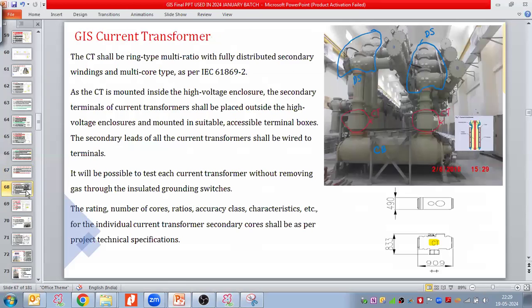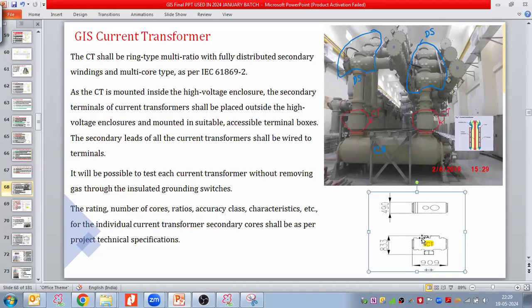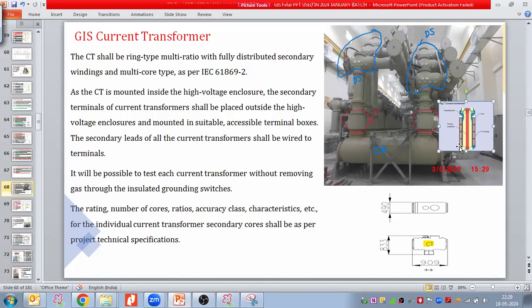Coming to the next equipment model, which is the CT model. First of all, how the CT model looks like. Here this is the GA drawing of the CT. CT here, CT here. It is the plan view and the side view of the CT. Inside the CT, we do the CT core assembly, like 1, 2, 3, 4. However many cores are required, that assembly we do inside here. And due to that, most of the time it looks circular in shape.